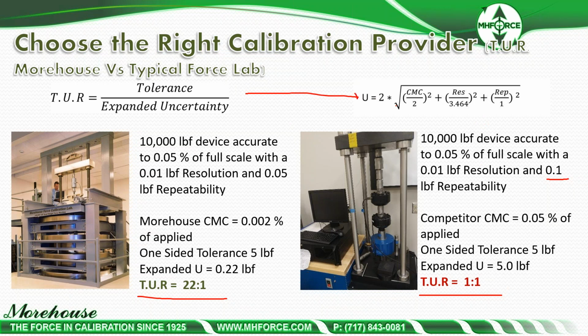at that handbook, there's all kinds of considerations on what goes in the denominator. At a bare minimum per ANSI Z540 is the calibration and measurement capability divided by the appropriate coverage factor that was used, resolution of the UUT, and repeatability of the UUT. There's other things in there. ILAC P14 also makes reference to having the short-term contributors. Those are resolution and repeatability as well. So we're basically using this denominator, which could have more than this in, but I'm using this because P14 kind of says this is the minimum.